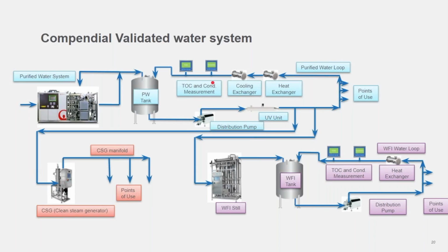So if we start on the left-hand side with the purified water generation system, in this particular case we have a softening RO-EDI system, the Orion unit as we call it, and this is hot water sanitizable. So we mitigate and manage our microbial growth. In terms of conductivity, we design it to produce water of less than 0.2 microsiemens going into the purified water tank. Should the purified water tank be full, i.e. no demand at points of use, then the water recirculates back within the system pre-RO. So it goes to the RO and CDI, keeping the water within spec, ready for when the purified water tank calls for more water.